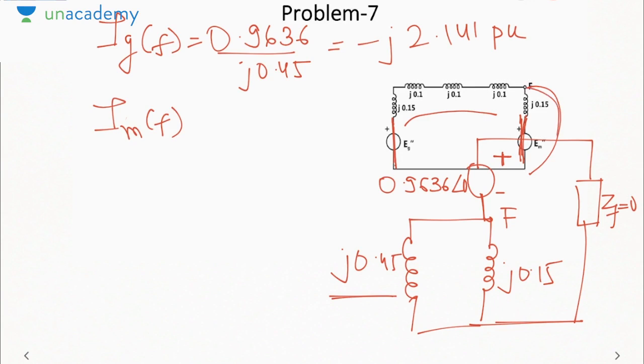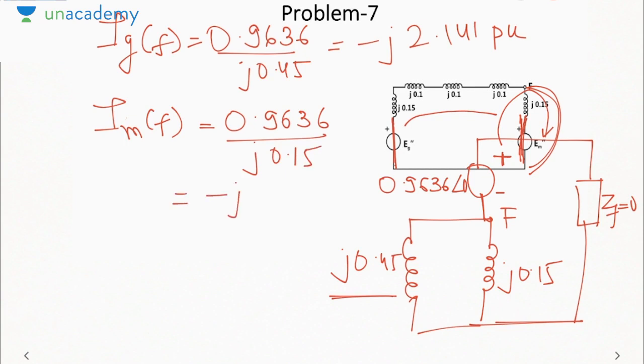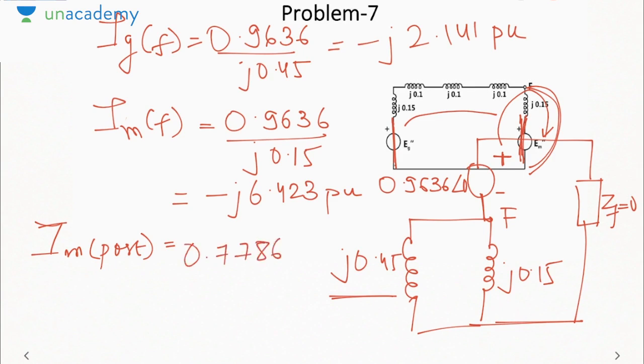Similarly, the motor current during the fault. Now when you ground this, the current will flow out of the motor, that is, the motor will start delivering the current. 0.9636 by J0.15. How much will this come out to be? Minus J6.423 pu. Earlier the motor was absorbing the current, now it is delivering the current. So the direction of current is reversed. So the total current in the motor, or we can say I motor post fault, will be the pre-fault current plus the during-fault current. The pre-fault current was 0.7786 angle 36.9. Now we will have to subtract this current because this current is going out of the motor. Earlier the current was into the motor.